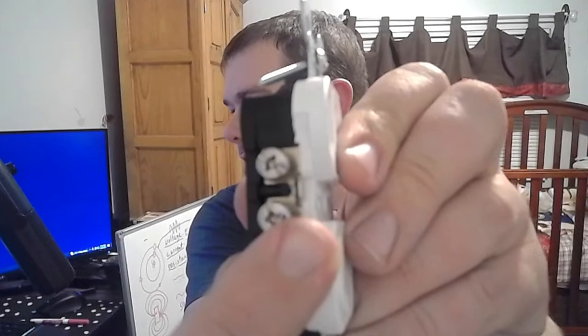Let's say you wanted this outlet right here always on, and this outlet right here controlled by a switch, a light switch. There's a tab right there on both sides. If you break that tab off, you essentially now have two circuits. This can be controlled by a switch, and the other one can be on all the time. It really doesn't matter. Or you can have each of these controlled by a different switch. Switch one, switch two. It's real simple.